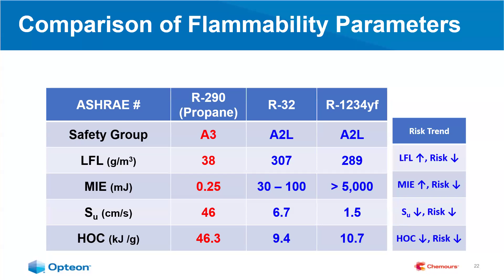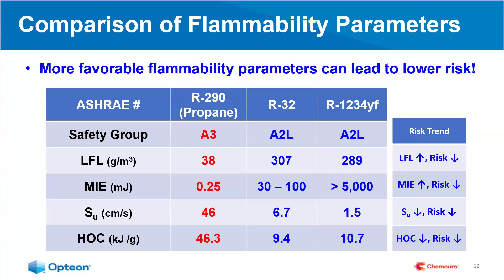Once you do get an ignition, you want to look at the severity by examining burning velocity and heat of combustion. For A2Ls, these values are much lower than R-290. The burning velocity of propane is 46 centimeters per second — it propagates very quickly — but for A2Ls, values are less than 10 centimeters per second, which you can walk faster than. The heats of combustion of an A3 are also much higher than those of an A2L. Together, lower burning velocities and lower heats of combustion contribute to lower risk. The more favorable flammability parameters of A2Ls help minimize the risk of moving to a flammable refrigerant.